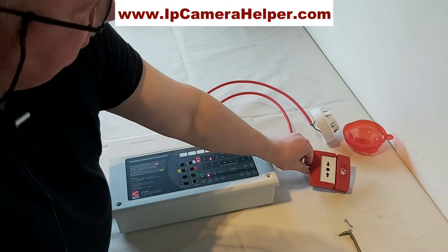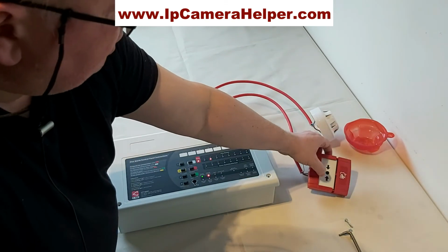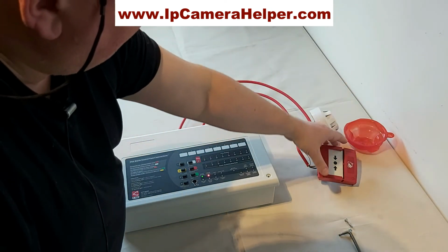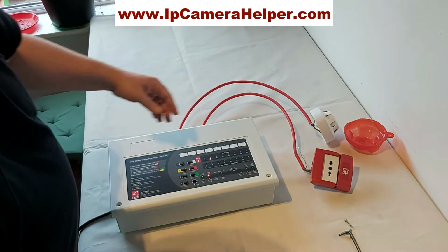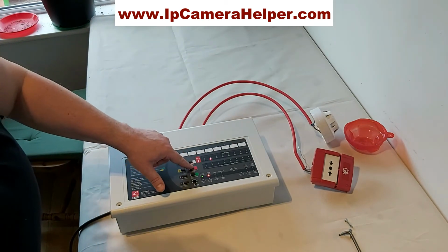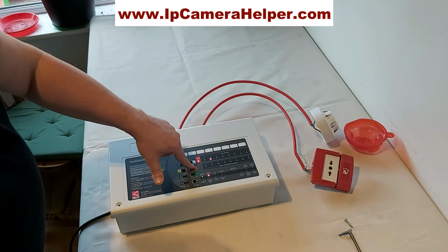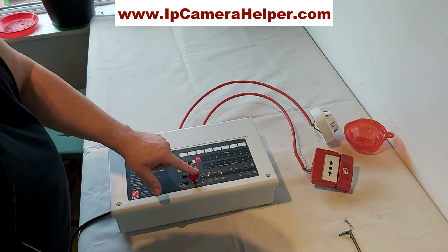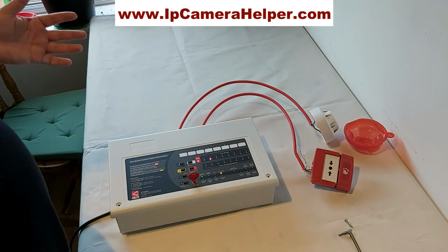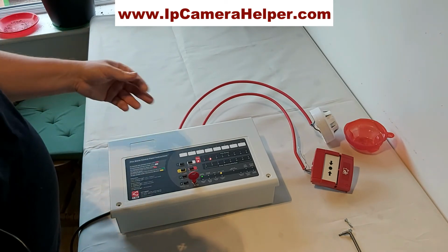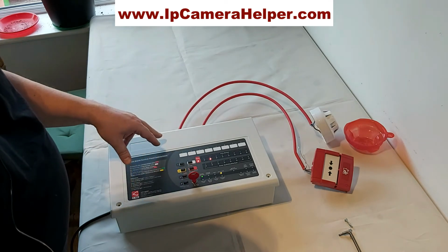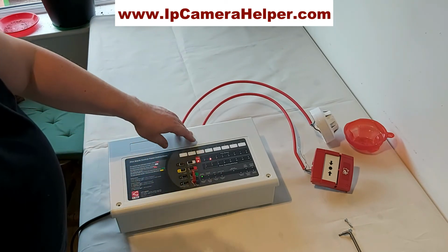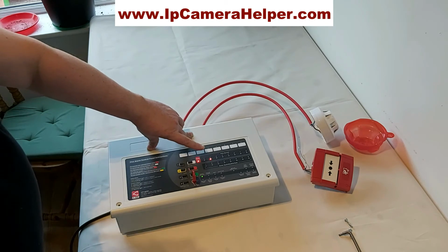Now we cannot reset the fire alarm until the fire condition on the detector zone is removed. So either there's no fire or the break glasses are all reset. For the moment all I can do is silence the external sounders, but I cannot do this without the key. So I need the key, put the key in position 1, and that's my buzzer, which is silenced. But now it will be beeping, most likely. So you can still see the fire condition because it wasn't restored.